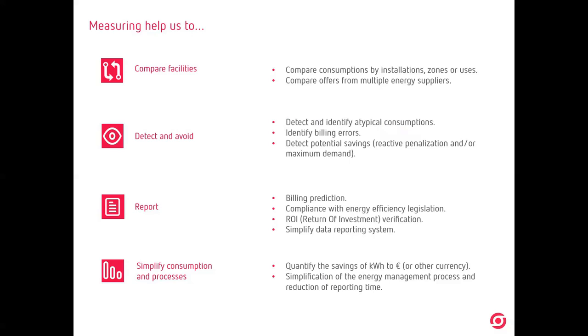It means that, for example, if we are inside an industry and the lighting consumption is 1% of the total, and we change all the lights to LED, okay, from conventional to LED, obviously we will improve. But if we modify the lighting consumption from 1% to 0.5%, yes, we will reduce, but these reductions will not have any impact at the end of the month in the bill. Okay, in this situation, if the climate is 50% of the consumption, we will have to think about improvement related to climate. Maybe changing the climate stations, maybe changing the insulation of the roof, or whatever.